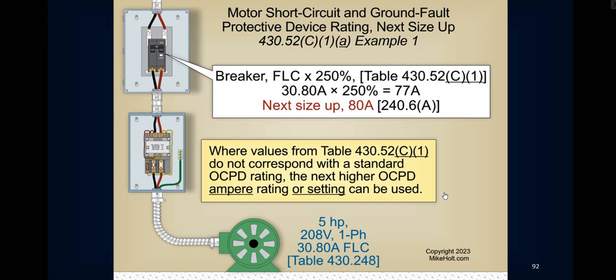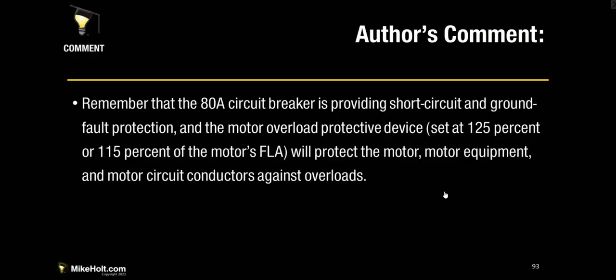Where that reverses is overload protection. When you are calculating, you get to the point with overload protection, you cannot round up. It goes down. Okay? Remember that the 80 amp circuit breaker is providing short circuit and ground fault protection, and the motor overload device set at 125 or 115 on the FLA will protect the motor equipment, and motor circuit conductors against overloads.